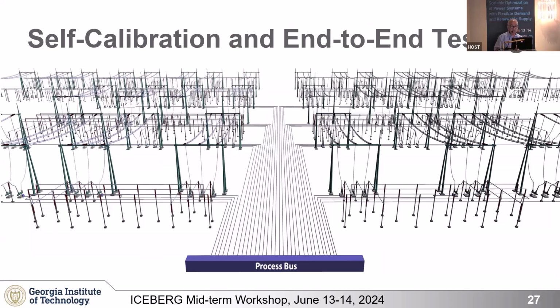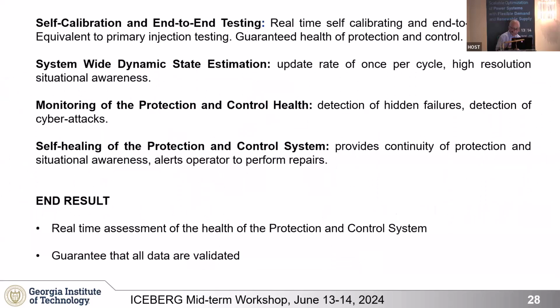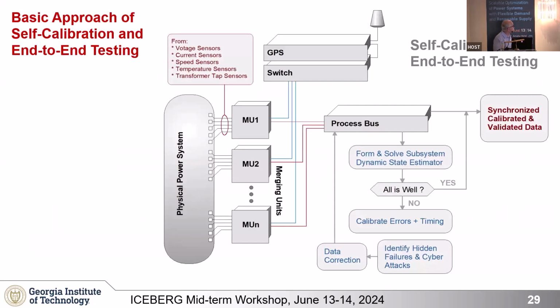Self-calibration and end-to-end testing is also a very important procedure. Think about it this way: we take all the data—the power system, the merging units generate the data, we go to the process bus where all the data is located. Doing the dynamic state estimation, we can see if there are calibration errors, timing errors, and so on. If that's the case, we can use the results of the dynamic state estimation as the calibration meter to correct that, and I'll show you in a second how this is done.